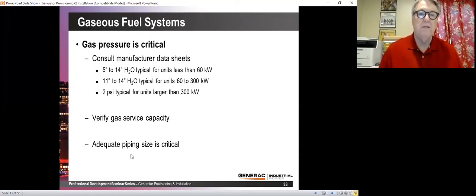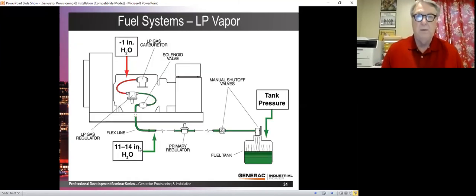Make sure your piping size is appropriate. This is the biggest problem we have on natural gas generators. People undersize the pipe. As I mentioned earlier, Power Design Pro, the free generator sizing software from Generac. You can get it free from www.generac.com, and it has a provision there, if you have a natural gas generator, to size your pipe for you, and it will have all of the gas flows and pressures right there. You just put in the length of your pipes and how many T's and 90s and so on. It will tell you what size pipe to use.